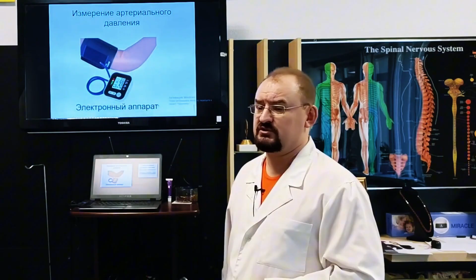Now, there are electronic devices. A person puts the cuff on their arm just the same, presses a button, and it automatically inflates, automatically deflates, and records the measurement. It electronically detects the moment when the bloodstream starts to break through the compressed artery, when the cuff stops compressing the artery, and immediately records your upper pressure as 108 over the lower pressure of 69. Often the pulse is also measured right away. 78, the device calculates it automatically.